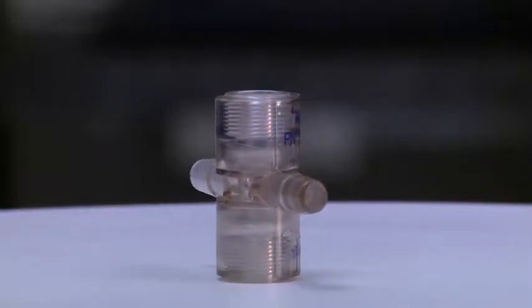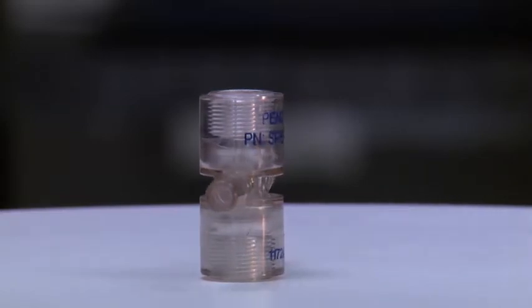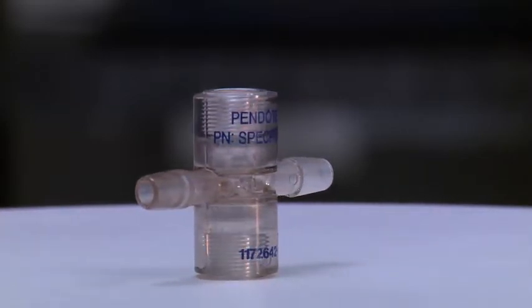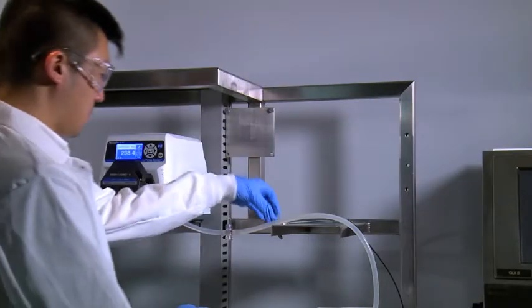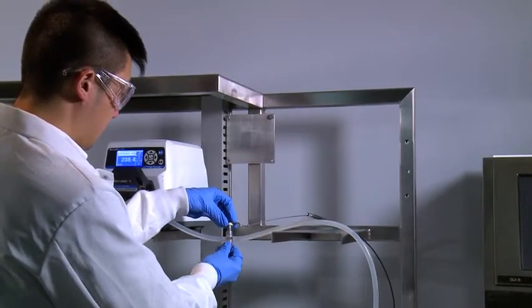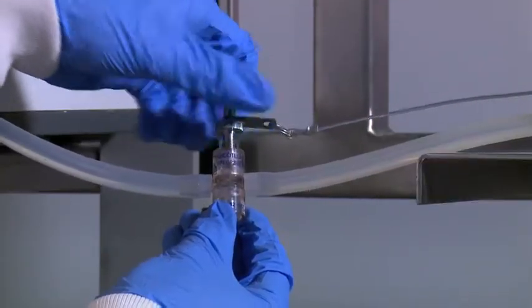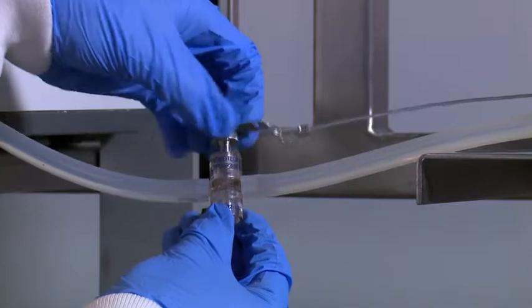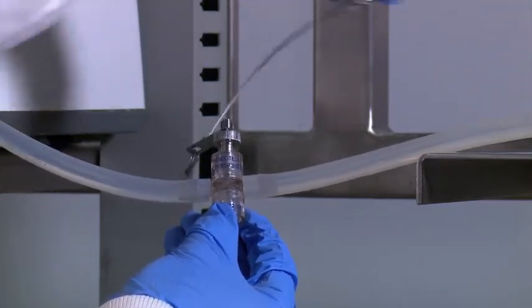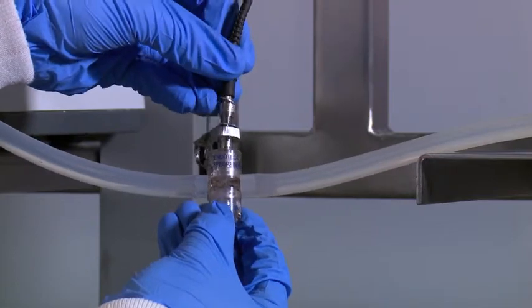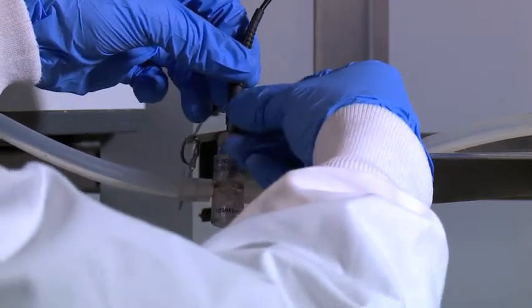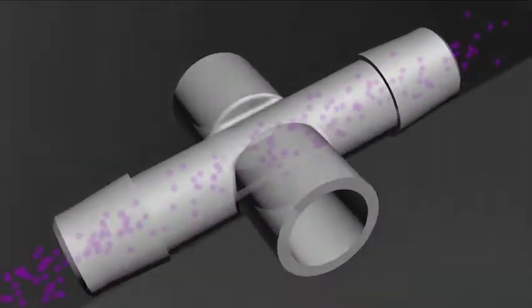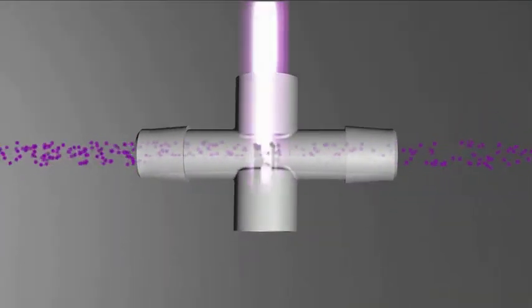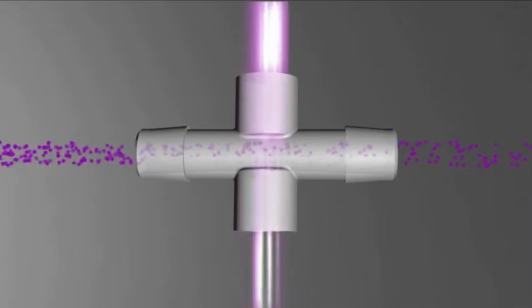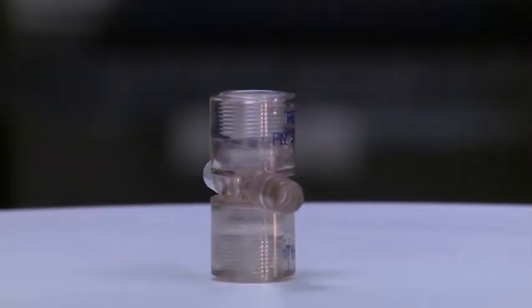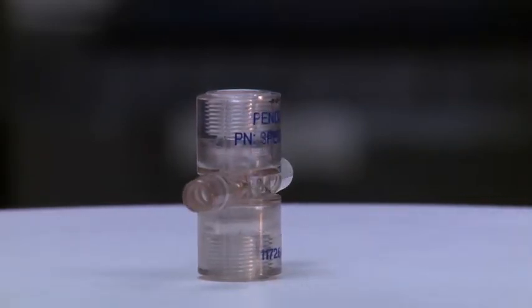These single-use sensors have a patented revolutionary design that allows the parts of the product that come in contact with the fluid to be disposable. The light source shines through a glass lens on the wall, and any transmitted light not absorbed travels to the other side, where there is another glass lens and a light detector to make the quantitative measurement. Optical couplers are installed on the single-use flow cell to focus the light across the fluid path. The stream to be measured flows between the lenses by way of tubing attached to the ends of the flow cell. Although designed to be disposable, these sensors are robust enough to be repeatedly cleaned and reused.